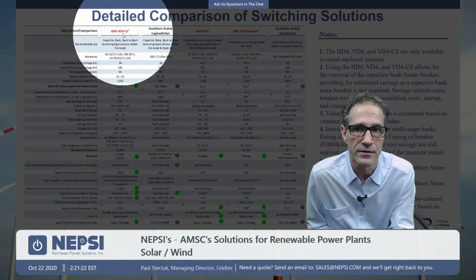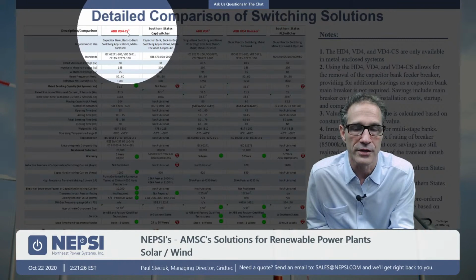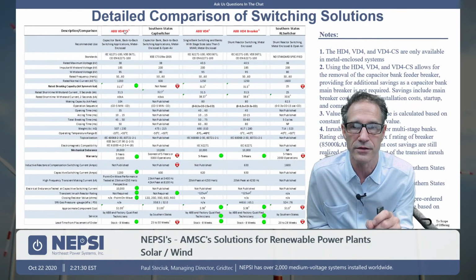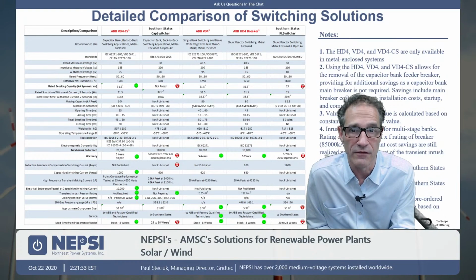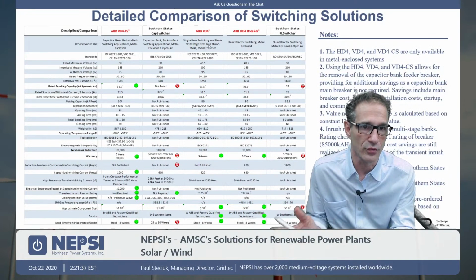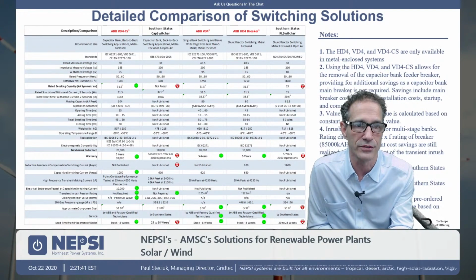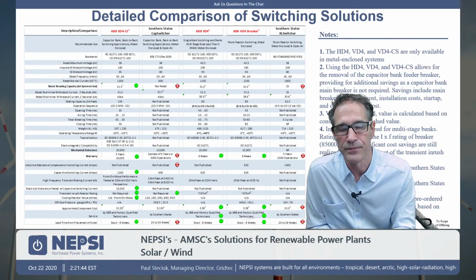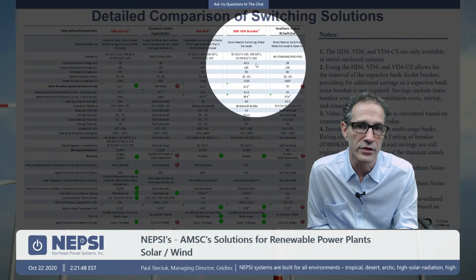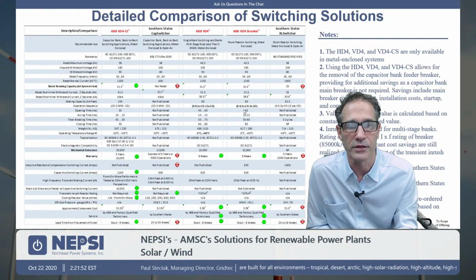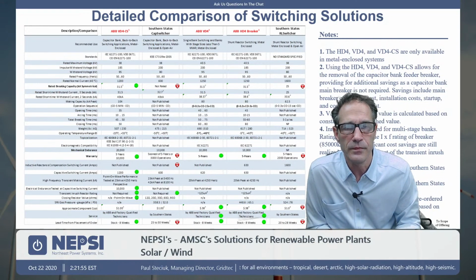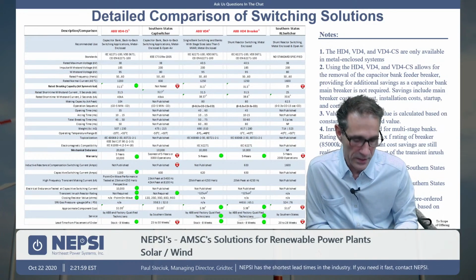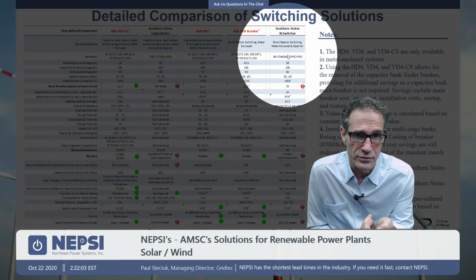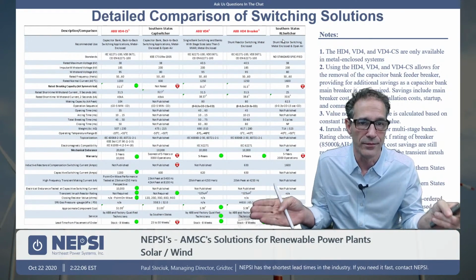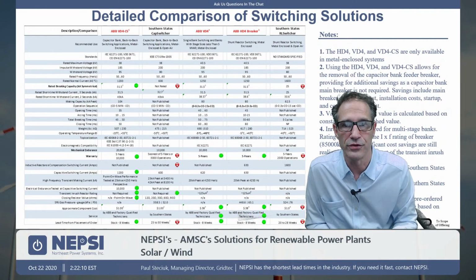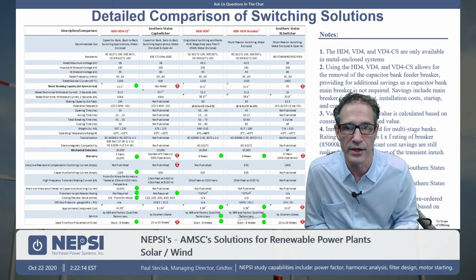The VD4CS is a vacuum breaker with synchronous closing technology. It uses servo motors. We have a whole video about this technology on our website. The VD4 is a standard C2 rated breaker. When I say C2 rated breaker, what I'm talking about is a breaker designed for capacitor switching. It means it has a very low probability of restrike. HD4 is an SF6 breaker, and we would typically use this for switching shunt reactor banks. And you want to use SF6 when switching shunt reactors. And then finally we have the RL switcher, which is a very large switch from Southern States. So these are, I would call, the major choices that you have when you are choosing which switching device to use. And these are the choices that we have and the ones that we most often use.